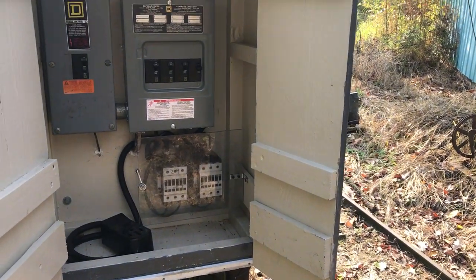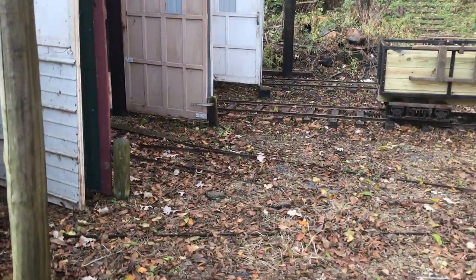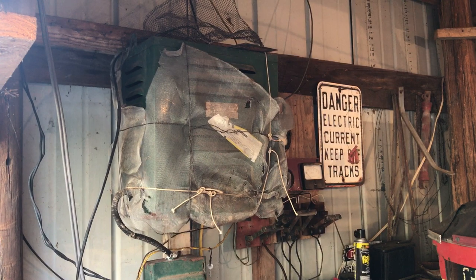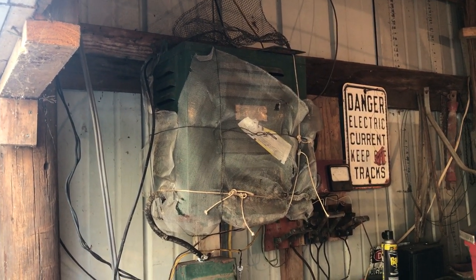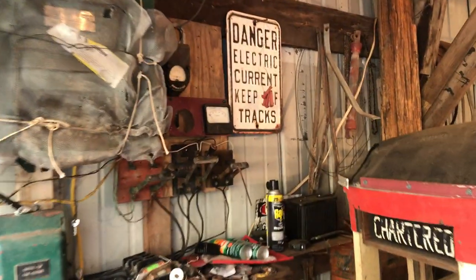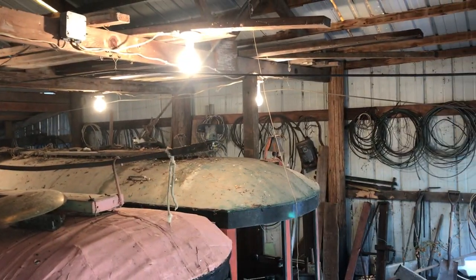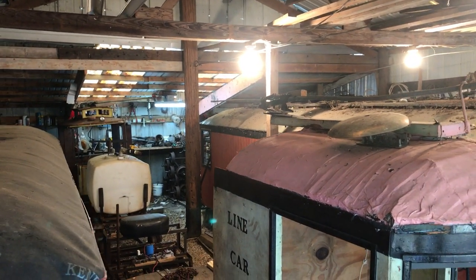There are two little contactors down there that energize those substations — it's done for lightning isolation reasons. When power comes in, here's the transformer for the barn, which is the first substation. It takes the 240 volts coming in — comprised of two legs of 120 volts to ground — and converts that to a single leg of 240 volts and ground. The knife switches are used to energize the other substations. That's the barn — I hope everyone enjoyed the tour! Have any questions, let me know in the comments. Thanks for watching.